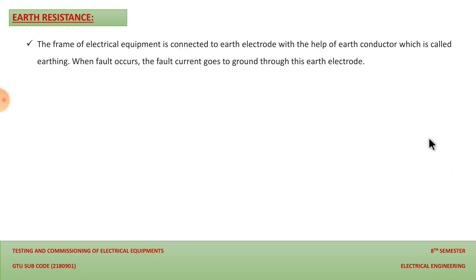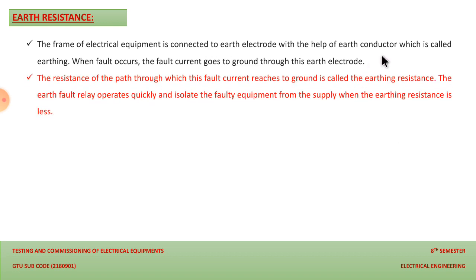So this is the phenomenon which takes place during the earthing fault, or we can say the discharging current is transferring through any equipment. So the resistance of the path through which the fault current reaches the ground is called the earthing resistance. Means the path taken by the charges to discharge from the charged body to the ground. And the earth fault relay operates quickly and isolates the faulty equipment from the supply when the earthing resistance is less. So whenever we provide less earthing resistance, the earth fault relay will operate because of the heavy discharge through that earth wire, and the earth fault relay will give a command to the circuit breaker, and it will remove the equipment from the electrical supply, so that we can protect the electrical equipment.